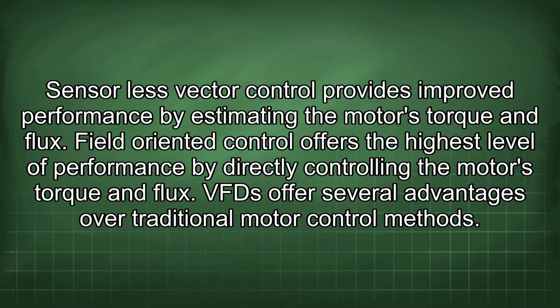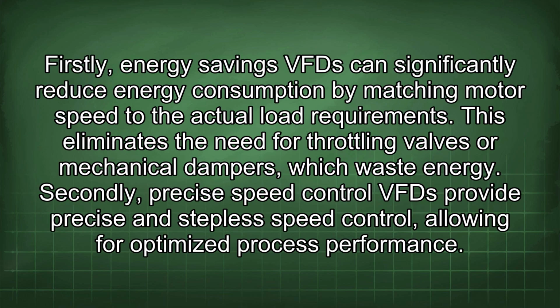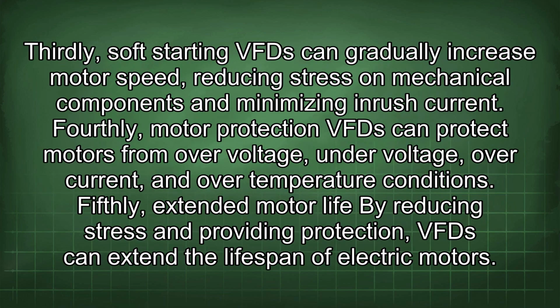VFDs offer several advantages over traditional motor control methods. Firstly, energy savings. VFDs can significantly reduce energy consumption by matching motor speed to the actual load requirements. This eliminates the need for throttling valves or mechanical dampers, which waste energy. Secondly, precise speed control. VFDs provide precise and stepless speed control, allowing for optimized process performance. Thirdly, soft starting. VFDs can gradually increase motor speed, reducing stress on mechanical components and minimizing inrush current. Fourthly, motor protection. VFDs can protect motors from overvoltage, undervoltage, overcurrent, and overtemperature conditions. Fifthly, extended motor life. By reducing stress and providing protection, VFDs can extend the lifespan of electric motors.